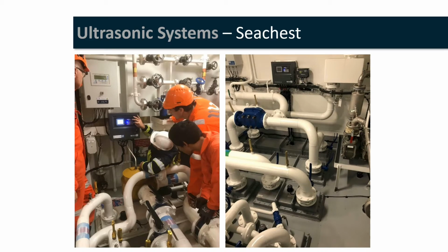Some chaps there looking at a control box, and I think on these pictures you might be able to just see down here there is a transducer on the lid of a cooling system. We've got some control boxes over here, and that is literally glued on the ring, and then that is screwed in with a little bit of grease. Another one here, and you can see that is going to be sending ultrasonic signals, another one there, through into the cooling system. These things also go on pipe work. So it's a very easy system to install, doesn't need to be dry docked, and this is one of the beauties with ultrasonics. It's actually a very simple system.